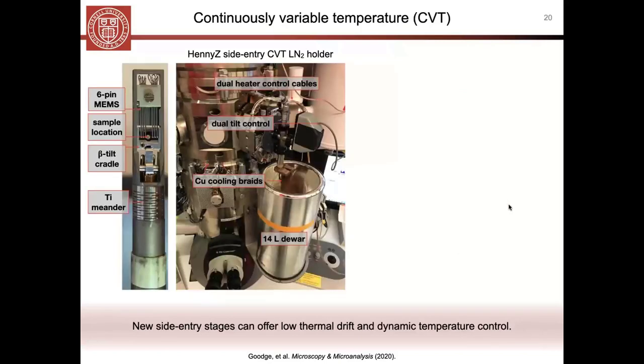In addition to the standard liquid nitrogen holders that we use at Cornell, we also have a more specialized holder from the HennyZ company, which is also side-entry liquid nitrogen based. The main benefit of this holder for the phase diagrams I showed you is being able to sweep the temperature. Using liquid nitrogen, we cool this holder down to a baseline temperature around 100 Kelvin.